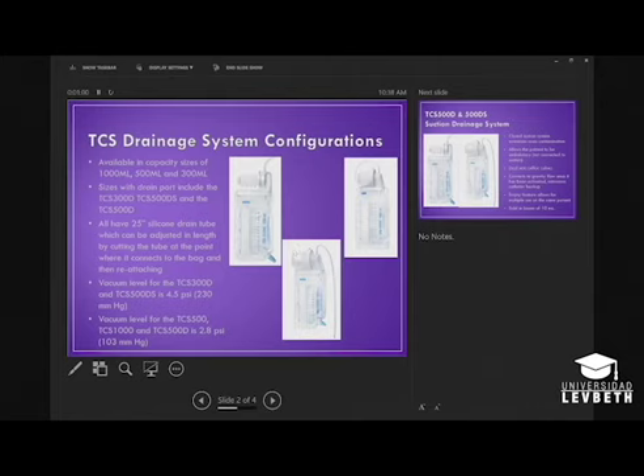Each bag has a drain port on the bottom. These are used for all your general abscess drains where they want suction. You would compete with just a typical gravity bag, a 600 ml gravity bag. They won't usually use these in biliaries and nephrostomies, because you don't want suction on the organ. And the 1000 ml bag doesn't have a drain port. They all come with a 25-inch silicone drain tube that can be adjusted. You can actually cut and pull out the luer and reattach the luer to the bag depending on the patient, since some are taller, some are smaller. They don't want a long tube hanging out.